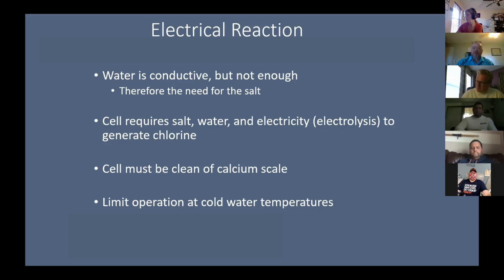All right. So the reason why you want to make sure that you're adjusting the output based on water temperature changes is because your chlorine demand is reduced when it starts getting colder. When it gets to a certain point, like I said, the unit will shut off automatically. I can tell you the Autopilot itself is the only one that will operate under cold water conditions. All right.